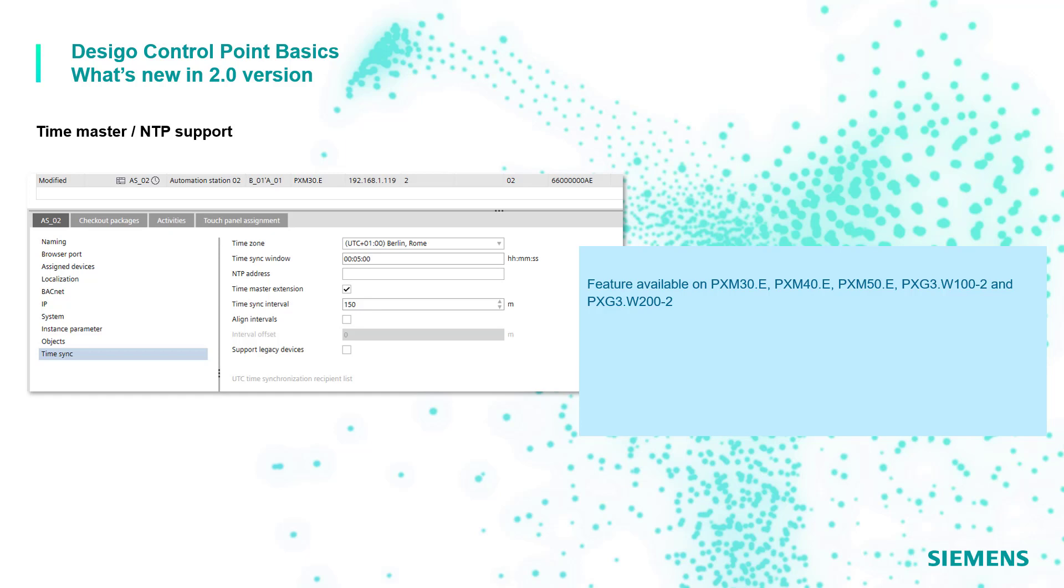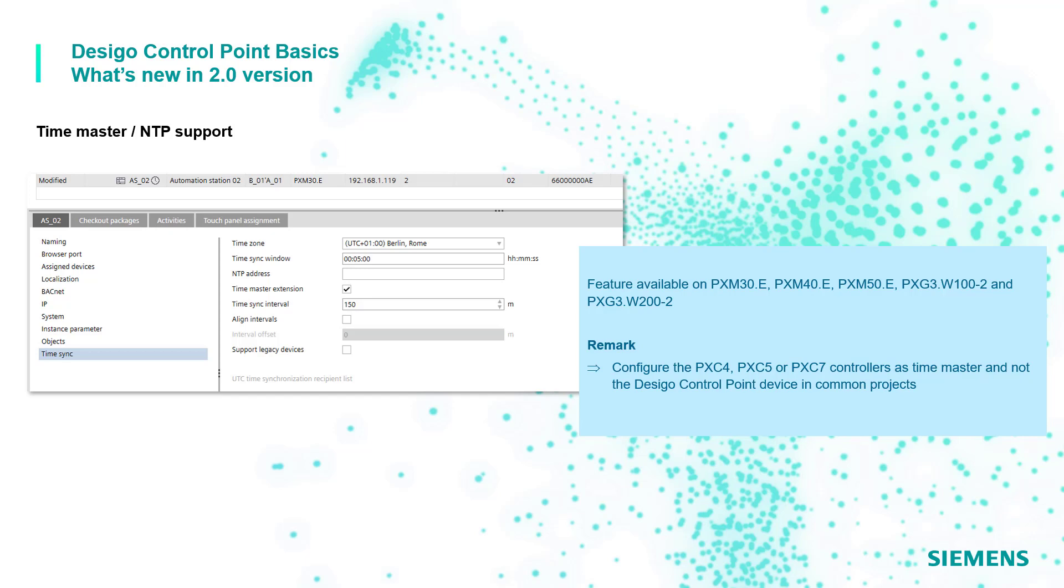However, as the control point devices are not equipped with a super capacitor, in case of power down they are not able to keep the date and time. So in case of projects that include also the PXC4, 5 and 7 controllers, it is recommended to configure the time master function on the automation controllers as they are instead natively equipped with a super capacitor and not on Desigo Control Point device.